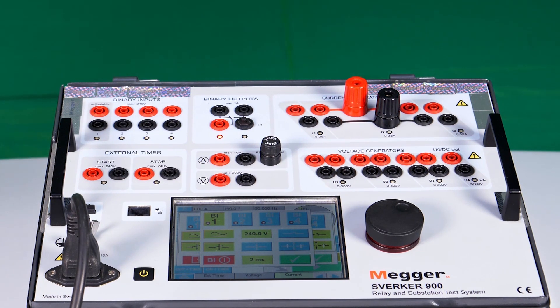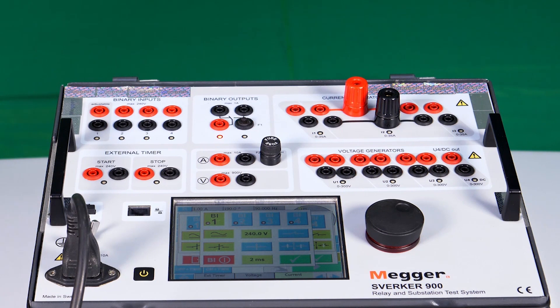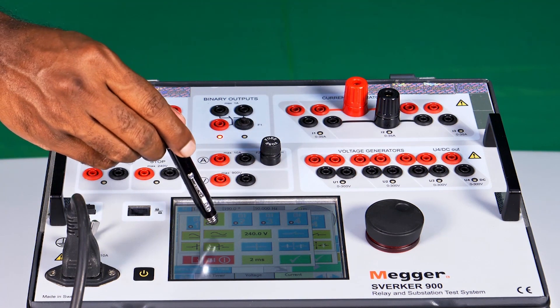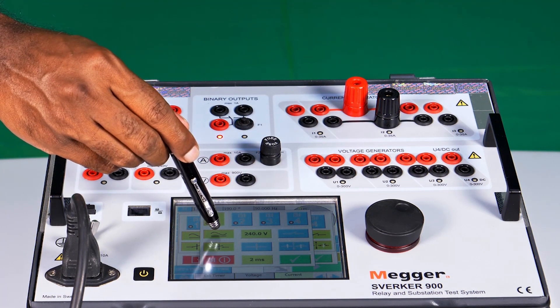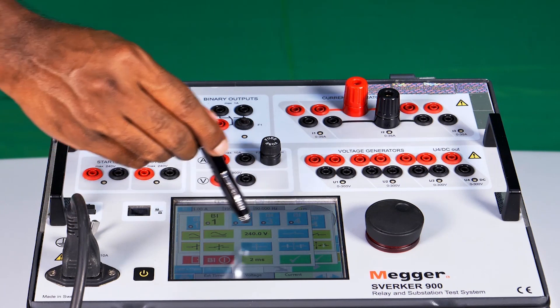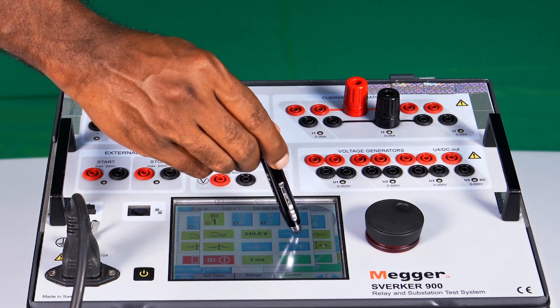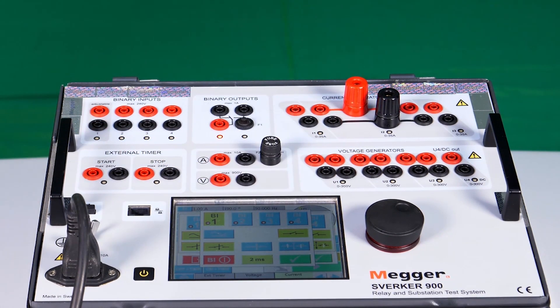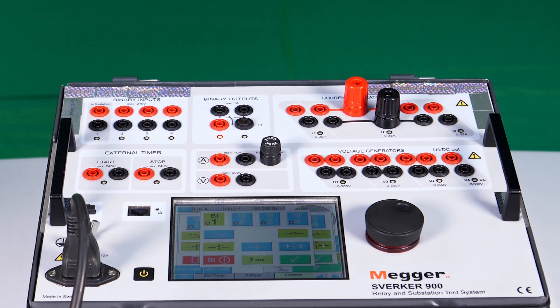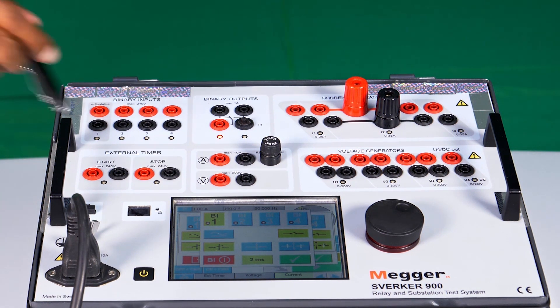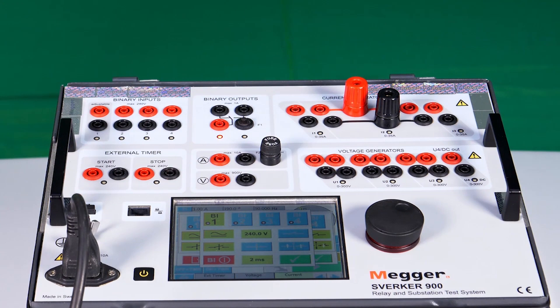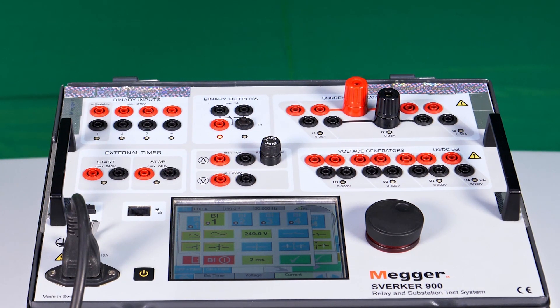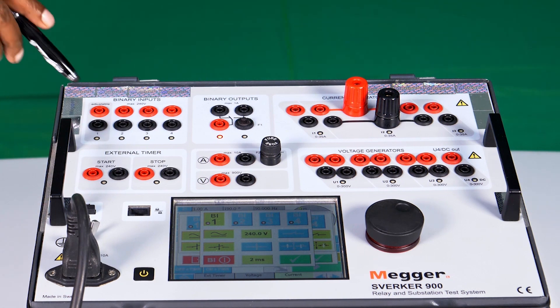Each binary input can be configured as with potential or without potential. This button, when enabled, will be with potential, and this is the option for without potential. When it is configured as with potential, the maximum voltage that can be applied is 240 volt as specified in the kit.